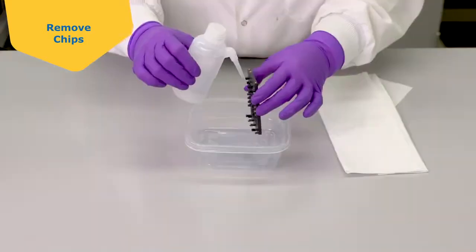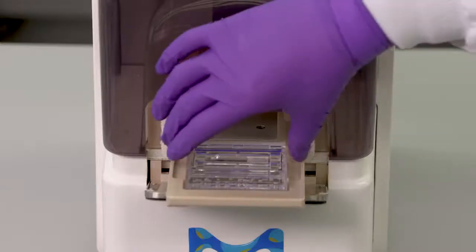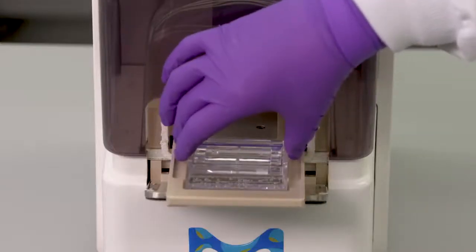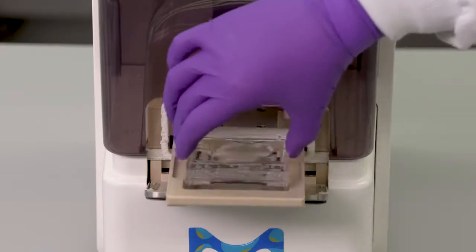Remove the IEF chip and Electrode Chip Plus. Rinse the platinum wire with distilled water and gently dry it. Remove the solution chip plus and PAGE chip. Discard remaining solutions as required by your local safety regulations.